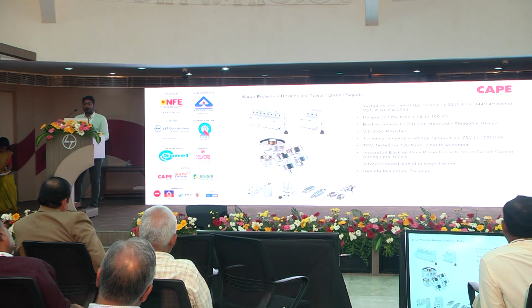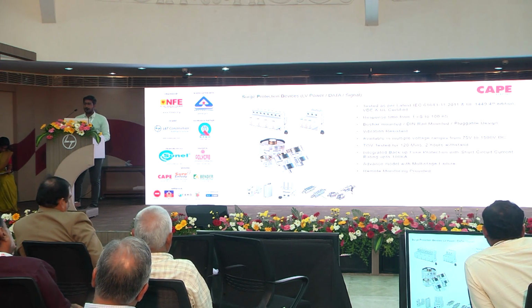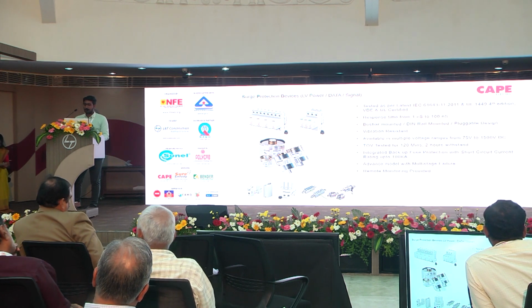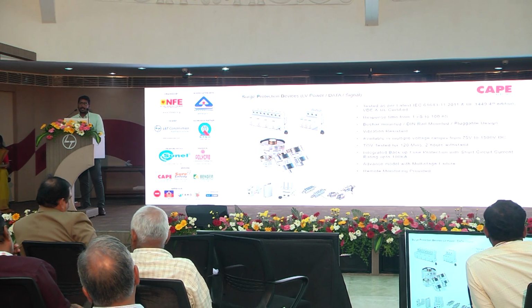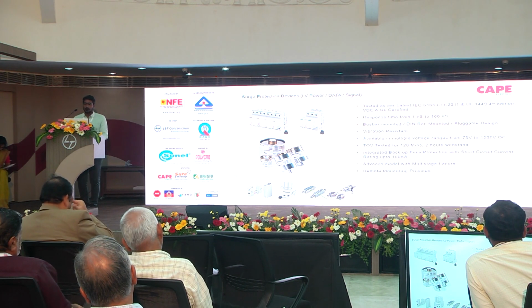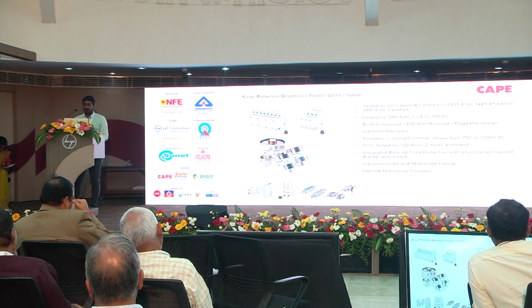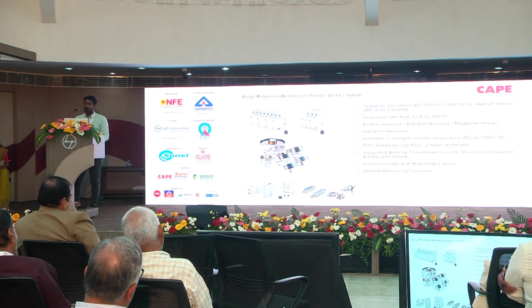Next, surge protecting devices, which will be used on LV power, data line, and signal line. Surge protecting devices are tested as per the latest standards IEC 61643 part 11 and UL 1449, which is the 4th edition, and our products are all UL certified. The response time for the surge protecting device is 1 nanosecond to 100 nanoseconds. We have models such as bus bar mounted, DIN rail, and pluggable designs, available with multiple voltage ranges from 75 volt to 1500 volt DC.